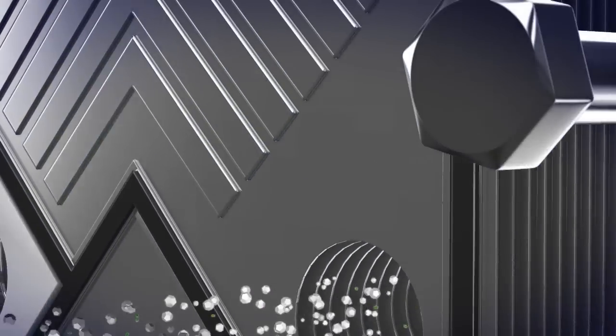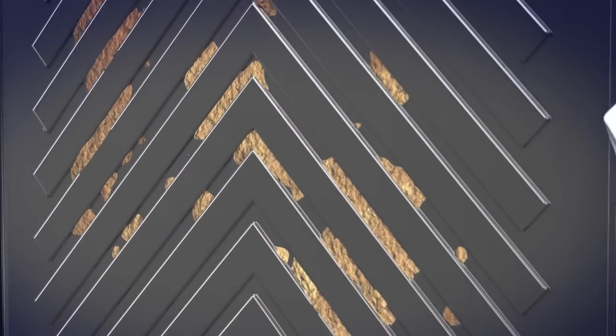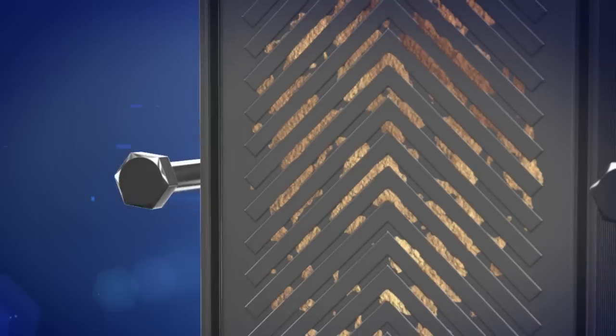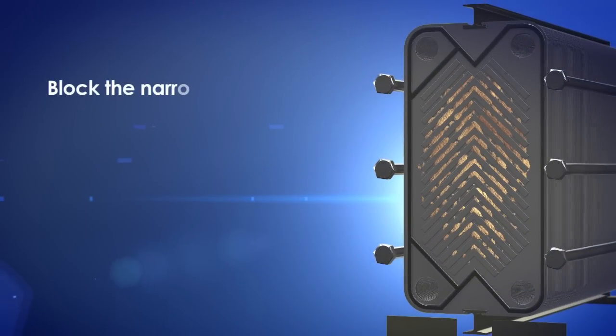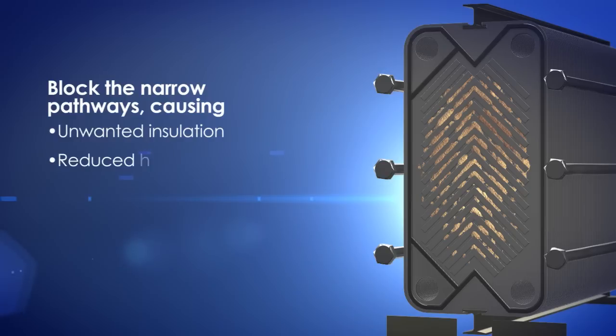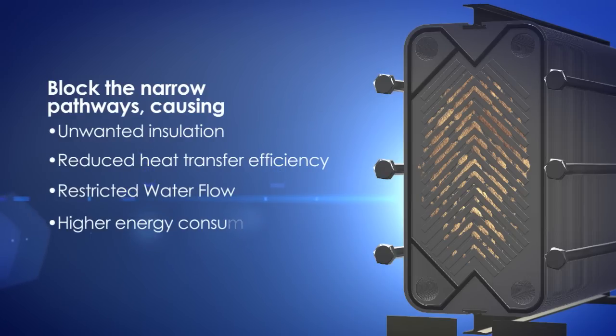Over time, accumulated scale on the heat plates, along with biofilm that consists of bacteria, algae and barnacles from the seawater, block the narrow pathways, causing pollution, unwanted insulation, reduced heat transfer efficiency, restricted water flow and higher energy consumption.